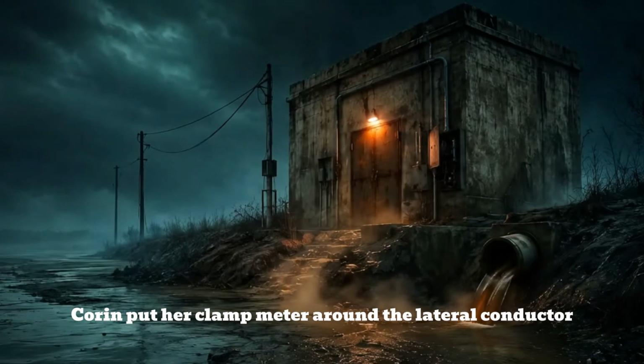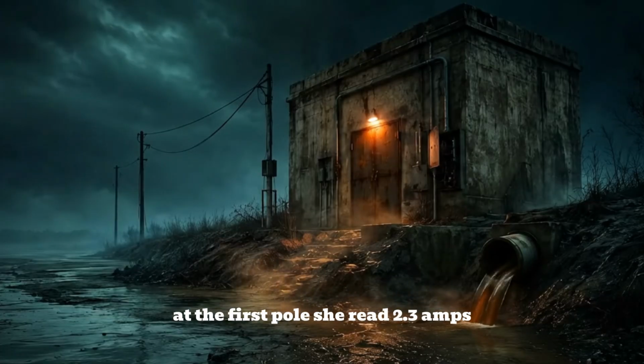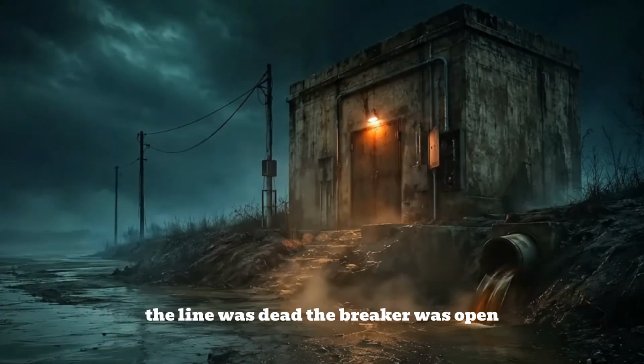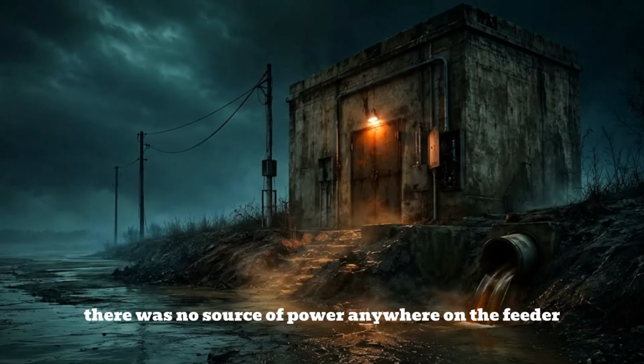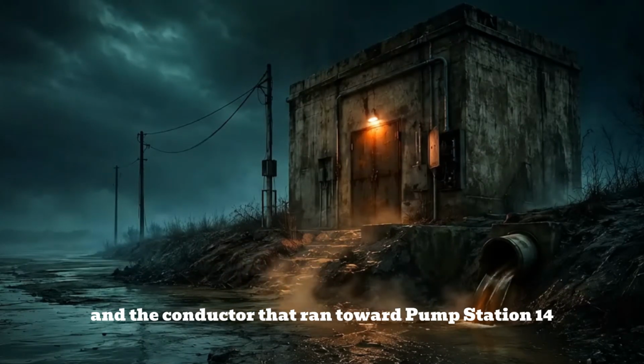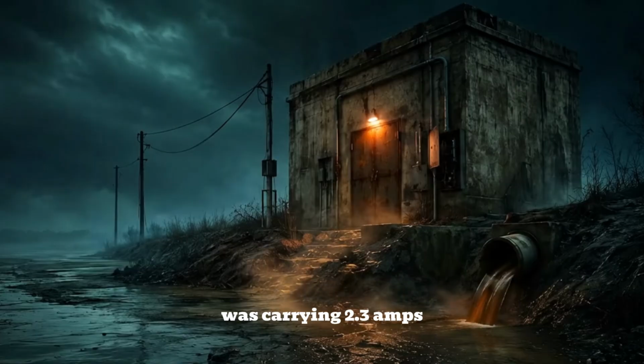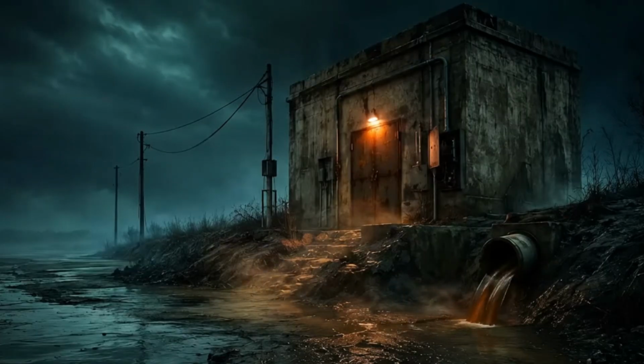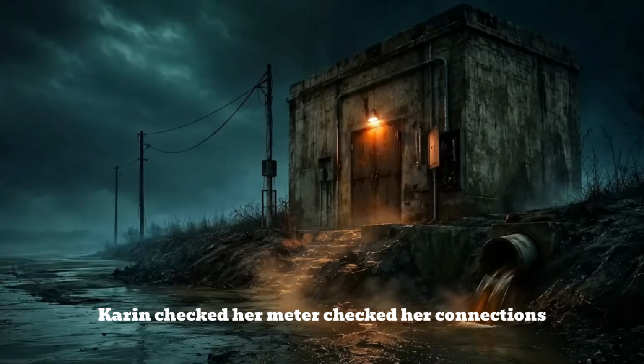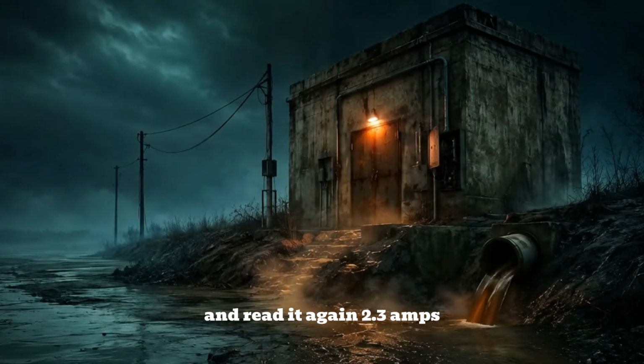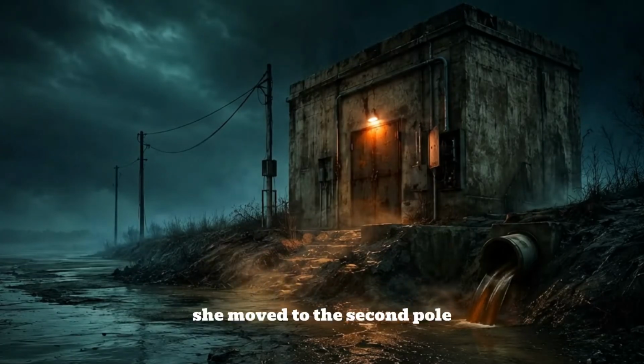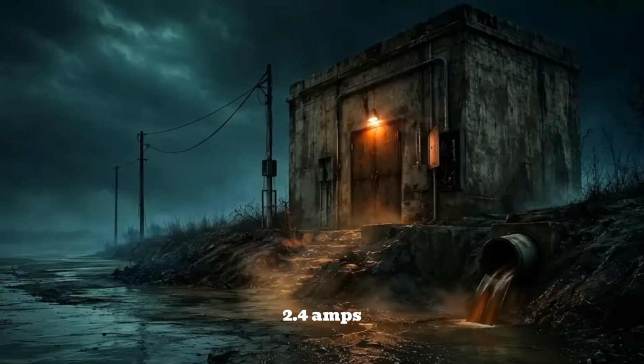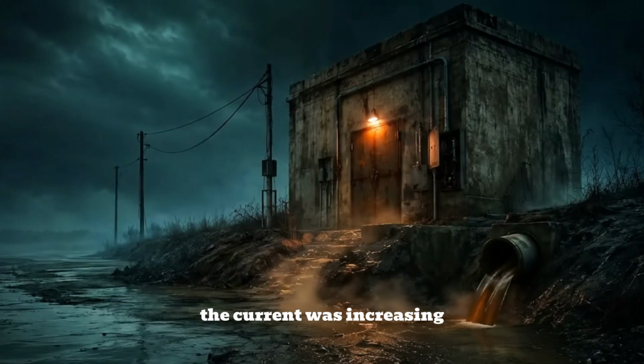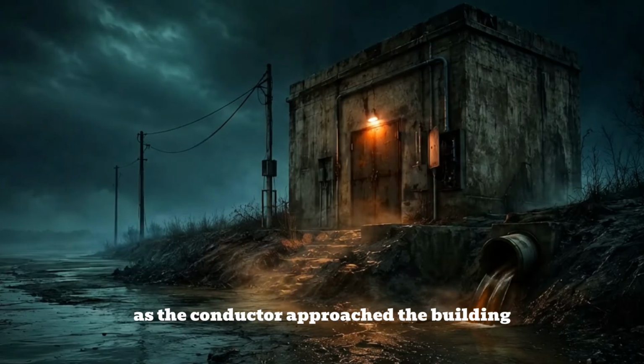Corinne put her clamp meter around the lateral conductor at the first pole. She read 2.3 amps. The line was dead. The breaker was open. There was no source of power anywhere on the feeder, and the conductor that ran toward pump station 14 was carrying 2.3 amps. Corinne checked her meter, checked her connections, and read it again. 2.3 amps. She moved to the second pole. 2.4 amps. The current was increasing as the conductor approached the building.